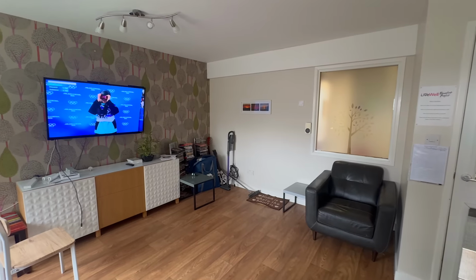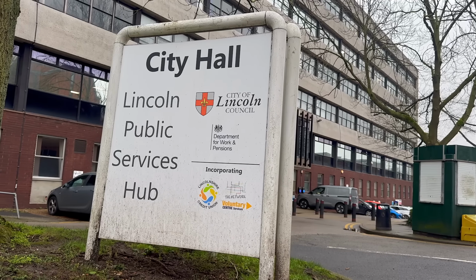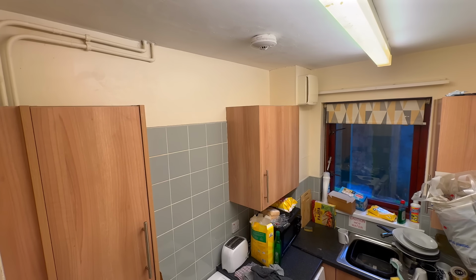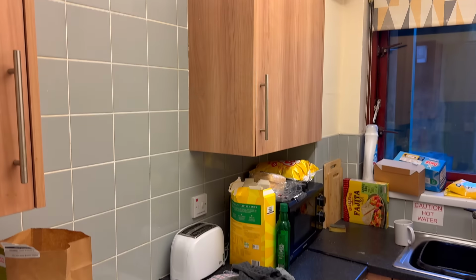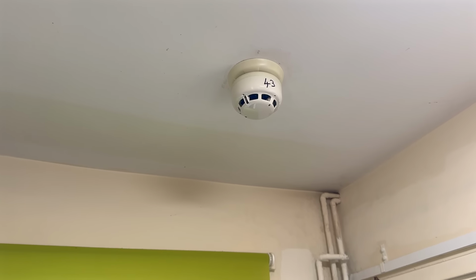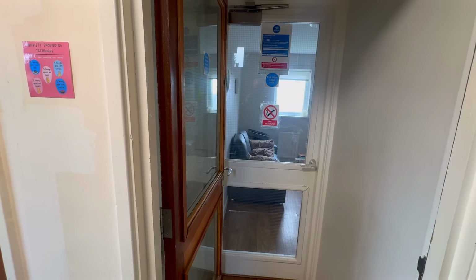Once a property is classed as a HMO, additional fire safety duties apply. Local authority licensing conditions often specify minimum fire detection standards, and these can exceed the basic domestic requirements. In addition, the Regulatory Reform Fire Safety Order applies to the common parts of the HMO, such as shared corridors and stairways. And it's this which creates an overlap between the fire detection in the domestic living accommodation and non-domestic fire detection required in the shared areas.